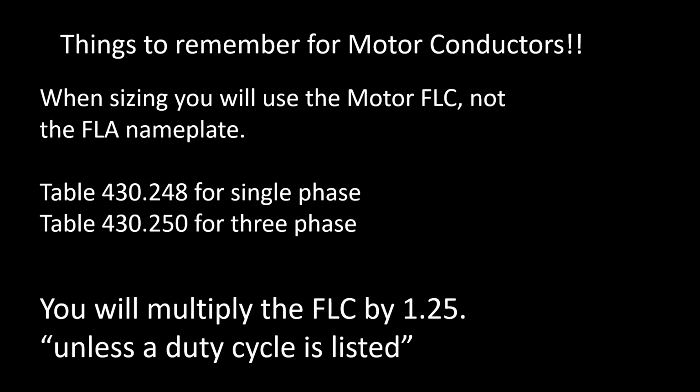Also, the other thing that we have to remember is that we're always going to multiply that FLC by 1.25 when we're sizing motor conductors, unless there's a duty cycle listed. So if there's a duty cycle, it says intermittent use, or it's going to be used for 15 minutes, or for 3 minutes, or whatever it is, then we're going to abide by some different rules, and we're going to dive farther into that next week.